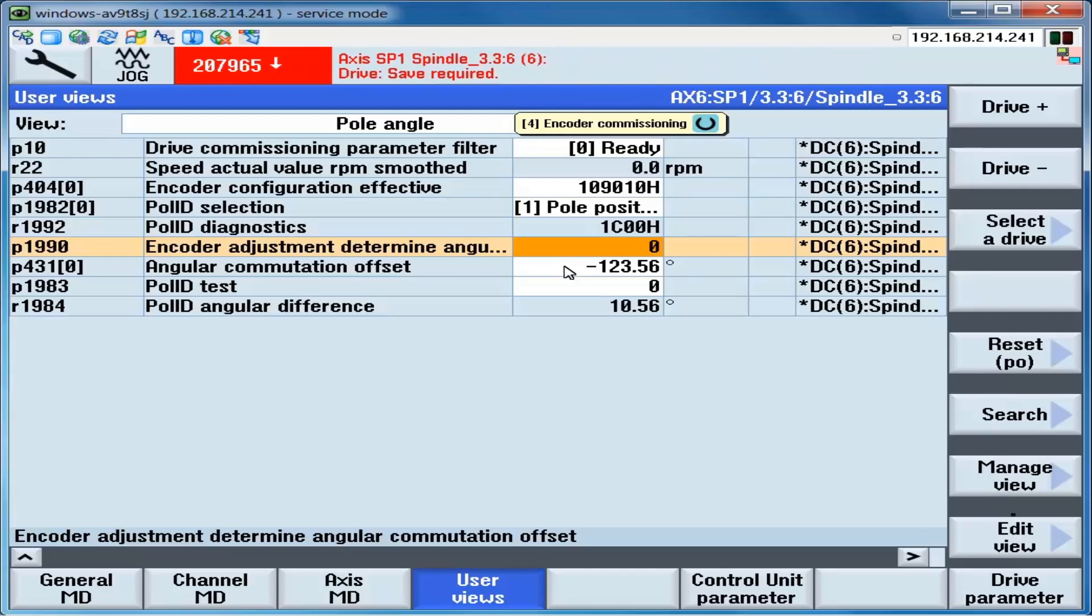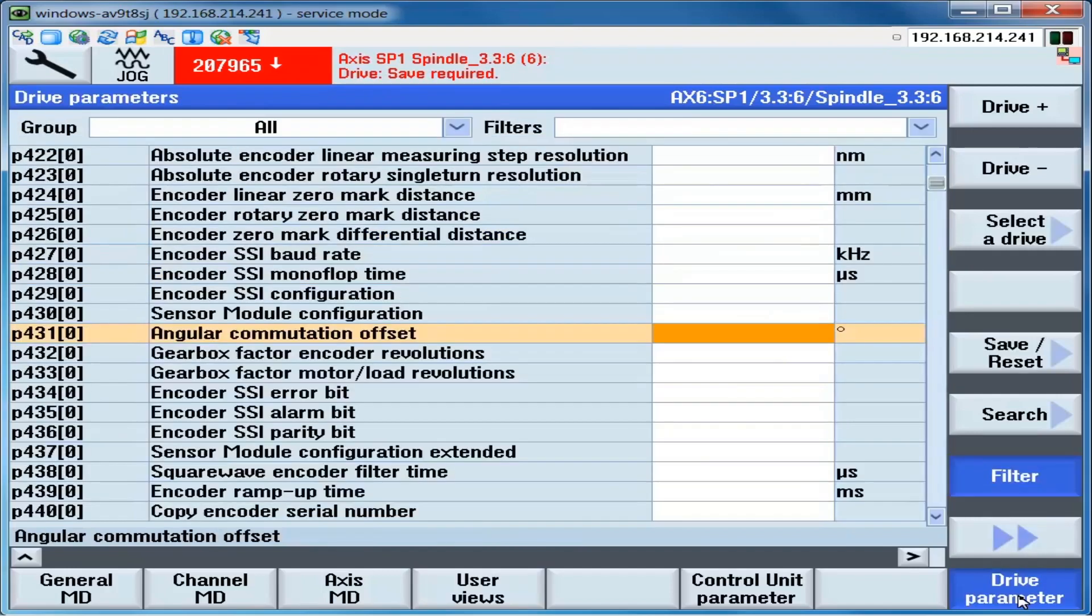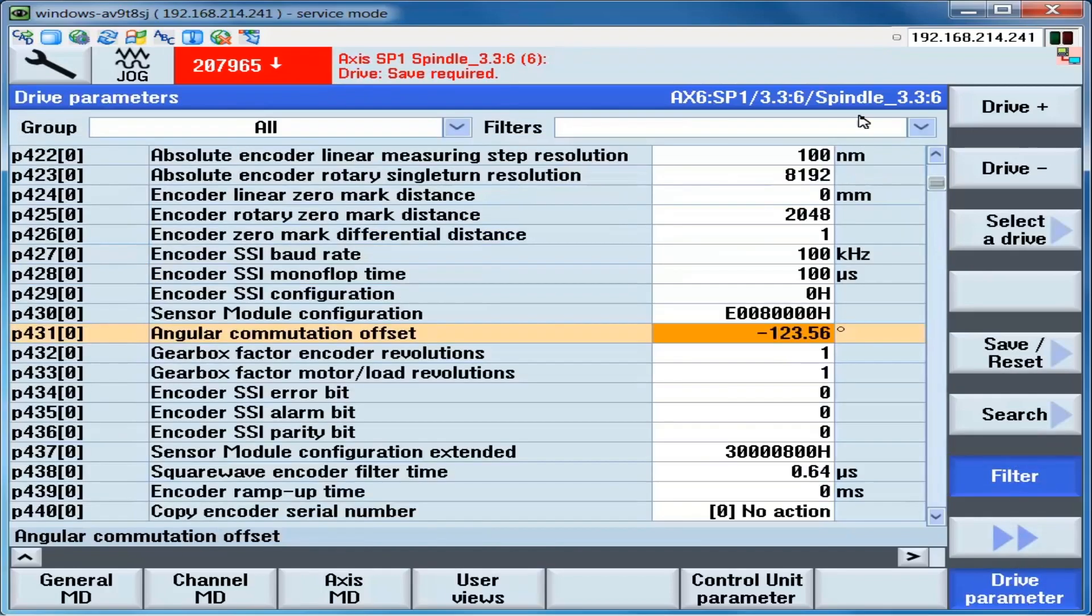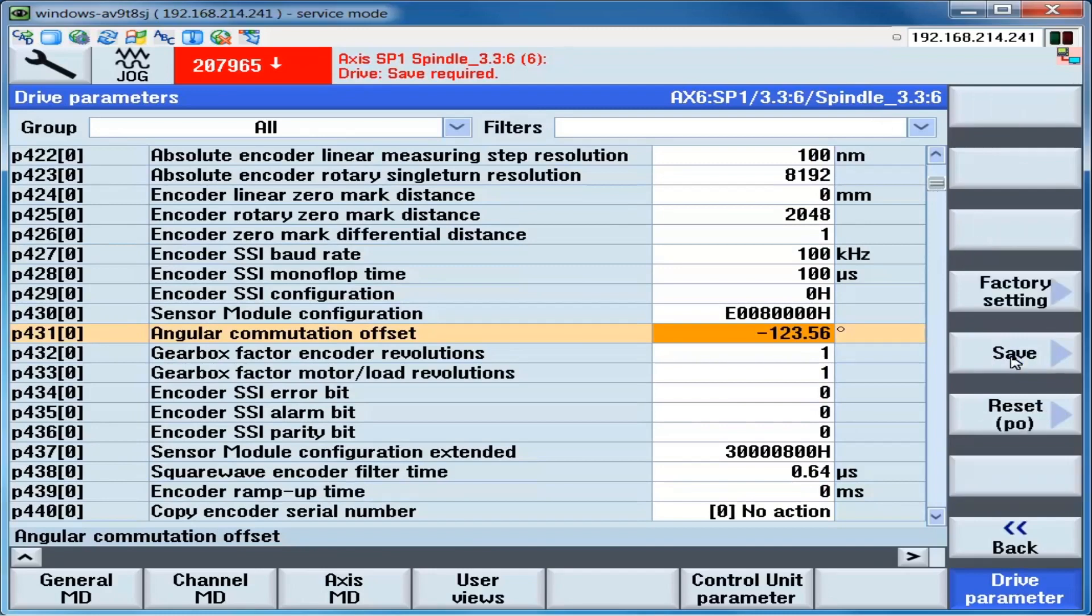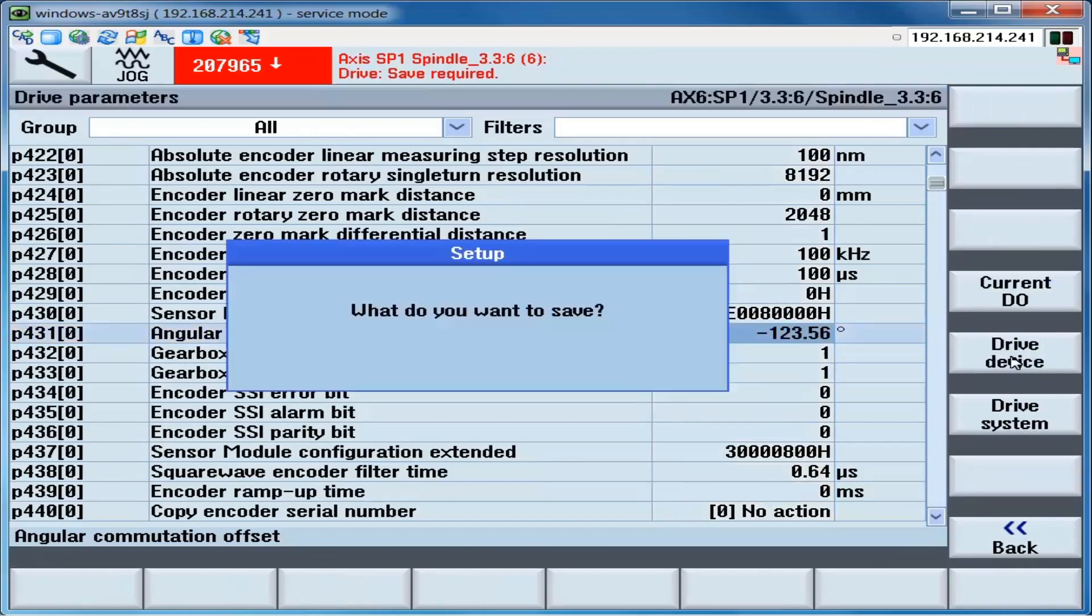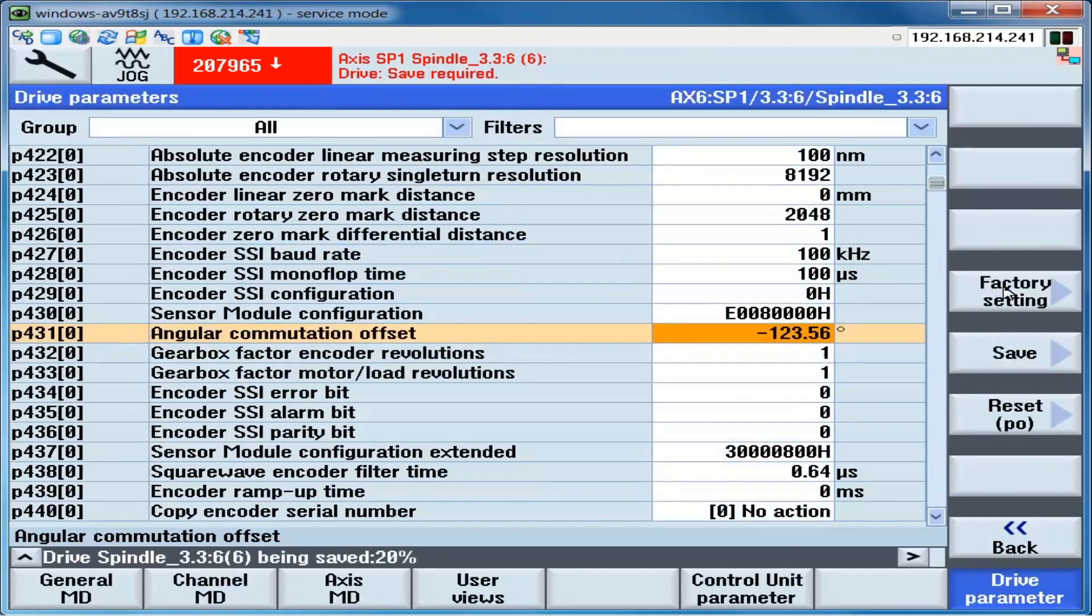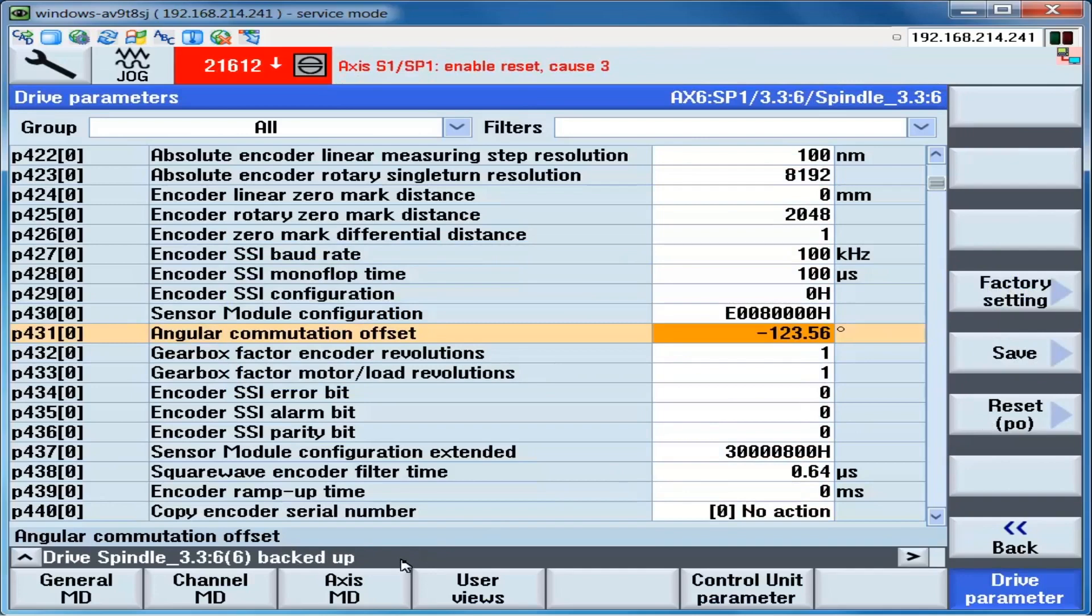The message 207965 appears, indicating that the drive data needs to be saved. We click on drive parameter. Make sure we're on the correct drive. Click on save reset. Click on save. Click on current drive object. Verify the message at the bottom that indicates that the drive has been saved.